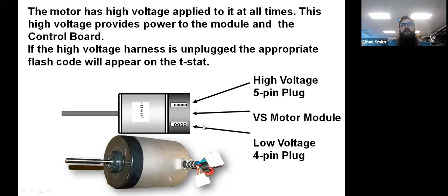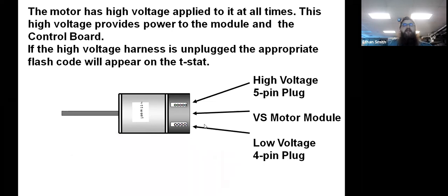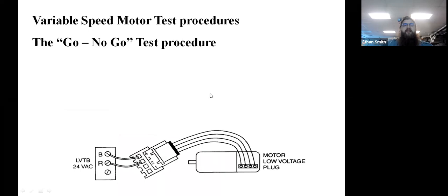After that, it gets a little more complicated because we're using a communicating signal on our low voltage pin. So we can't just check for voltage. We can do some voltage checks that'll tell us something, but the quickest way to test one of these motors is to do another go, no go test, where we're simply going to take the harness out of the board.